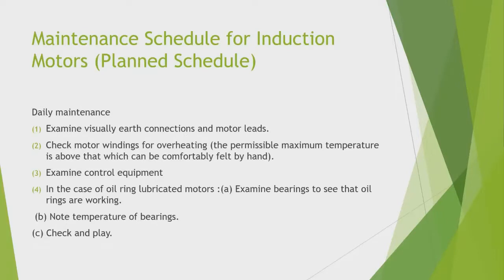Maintenance schedule for induction motor — planned schedule. Daily maintenance: examine visually earth connections and motor leads, check motor windings for overheating (the permissible maximum temperature is above what can be comfortably felt by hand), examine control equipment, and in the case of oil ring lubricated motors, examine bearings to see that oil rings are working. Check end play and note the temperature of bearings.